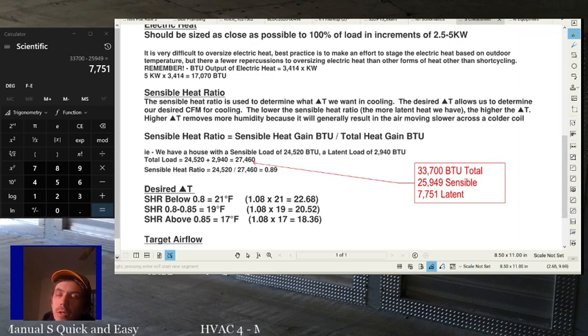Or you might be working with a manufacturer that has slightly lower output than you'd expect for a 3-ton unit or something. So you need to verify that you're putting out the same BTUs as you were before, assuming the original equipment worked well. If the original equipment didn't work well, then you should probably be doing a load calc. But if you're trying to avoid a load calc, it's a good extra step to look at the expanded cooling data of the original equipment and compare that to what you're putting in to make sure you're giving apples to apples.